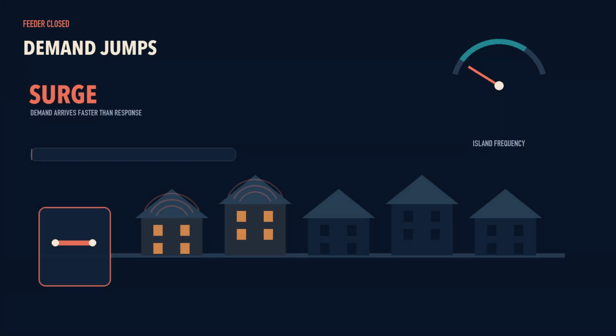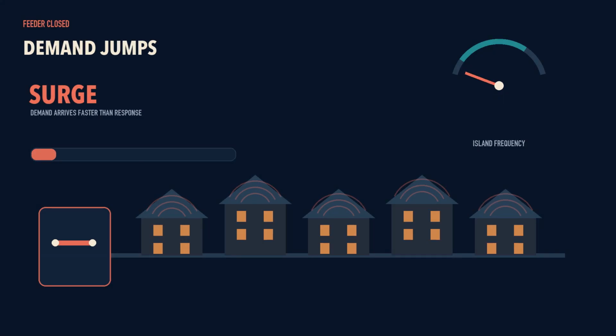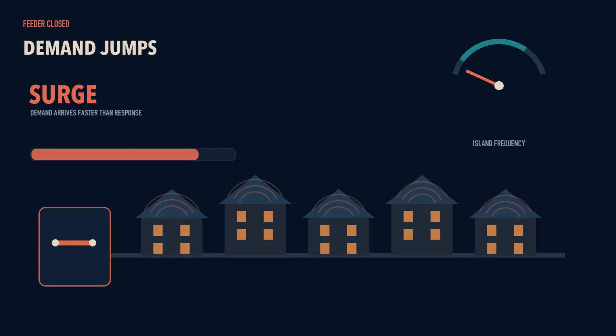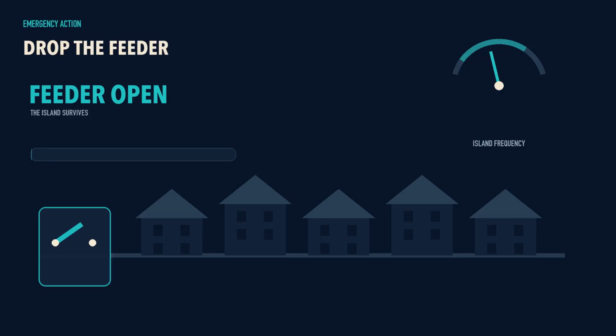The breaker closes. Demand leaps. Your frequency needle drops as generator governors pour in more water and fuel. They respond fast. The load arrives faster. The tiny grid begins moving toward its protection limits. You order the feeder shed. The neighborhood goes dark again just before the generators trip. It looks like failure from the street. From the control room, it is the decision that prevents the entire island from dying.